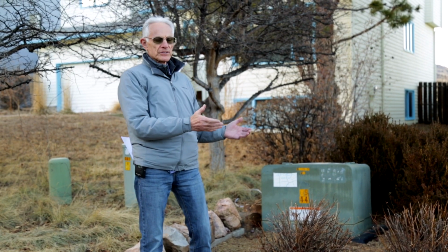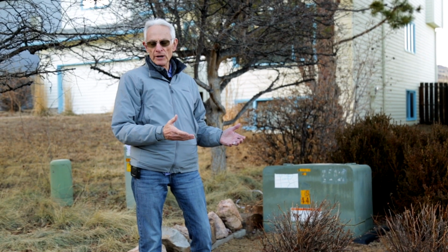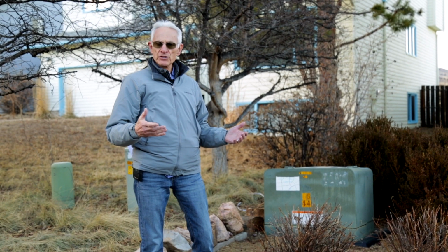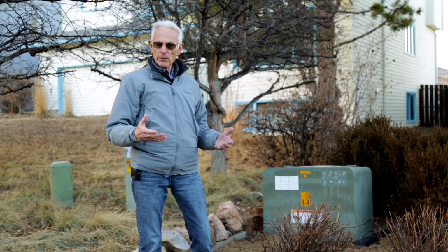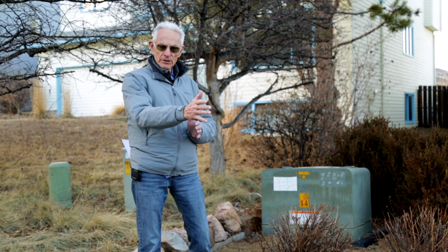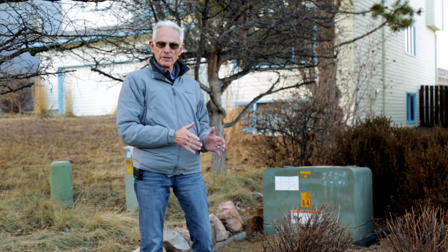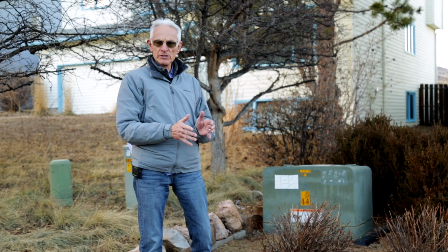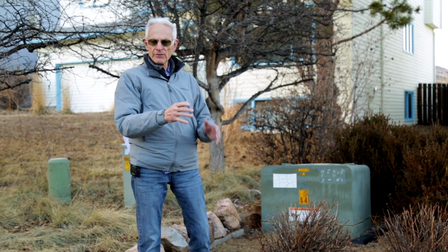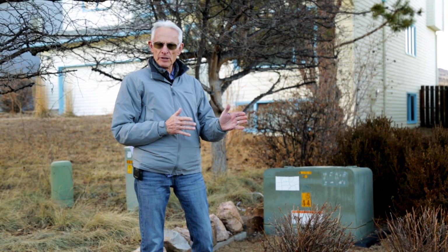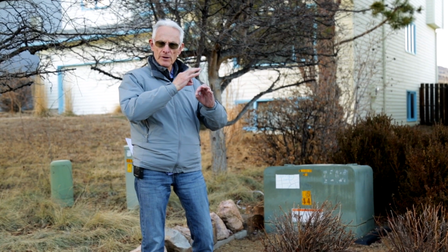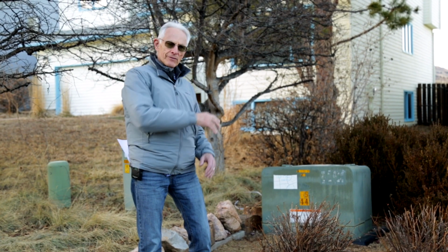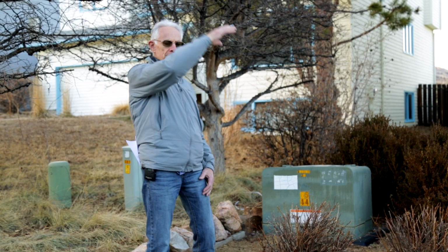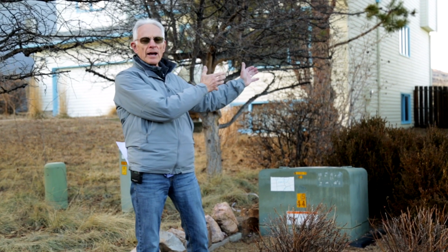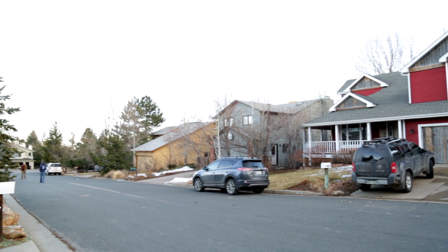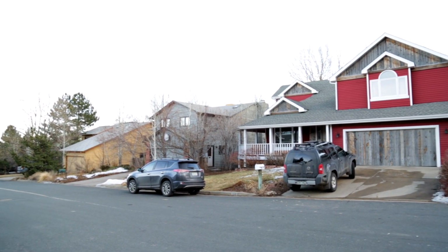This is a perfectly fine system, except in a situation where we have a distribution line issue, where we have unequal current flow, delivery and return wires that are buried in the ground. And when we have that situation, we have a net current, we have incomplete cancellation between the magnetic fields around the wires that we talked about earlier. And then we have a very large magnetic field that surrounds the wires, and it reaches out so far that it actually affects the homes along this buried distribution line.